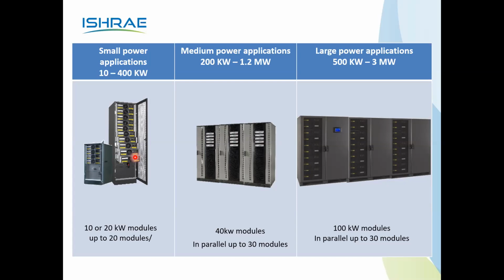That is the main thing. Cannot think about any kind of shutdown. No need to shut down the UPS systems, no need to drop the load, no need to transfer the load to the bypass. Without that, a modular UPS is possible. That is possible with the true modular UPS concept. There are two concepts available in the market: semi-modular and true modular. Semi-modular, it's a challenge. I'll tell you, semi-modular, it's a challenge. It may not be possible.